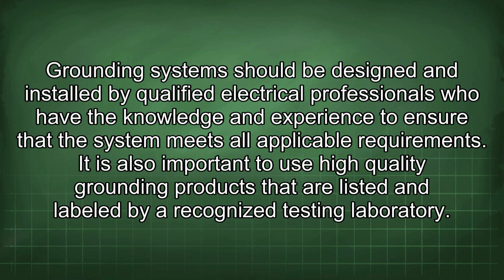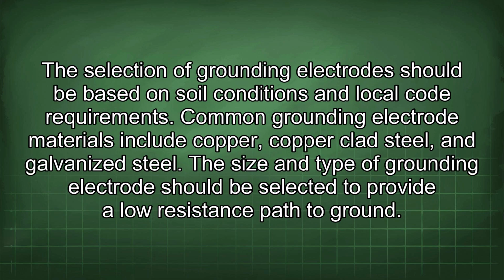Grounding systems should be designed and installed by qualified electrical professionals who have the knowledge and experience to ensure that the system meets all applicable requirements. It is also important to use high-quality grounding products that are listed and labeled by a recognized testing laboratory. The selection of grounding electrodes should be based on soil conditions and local code requirements. Common grounding electrode materials include copper, copper-clad steel, and galvanized steel. The size and type of grounding electrode should be selected to provide a low-resistance path to ground.